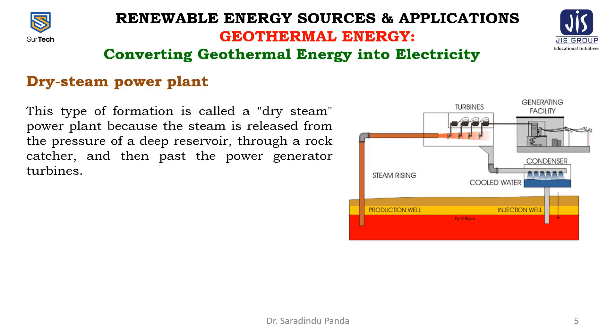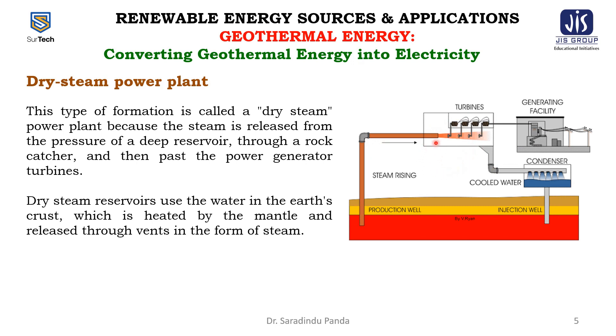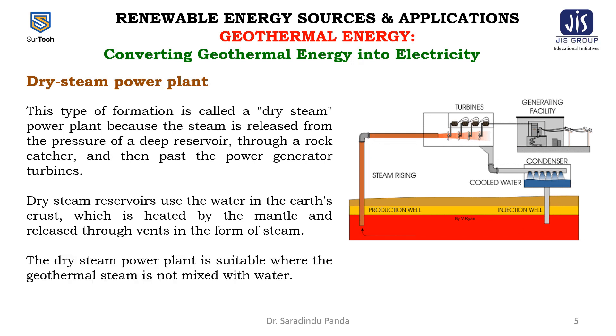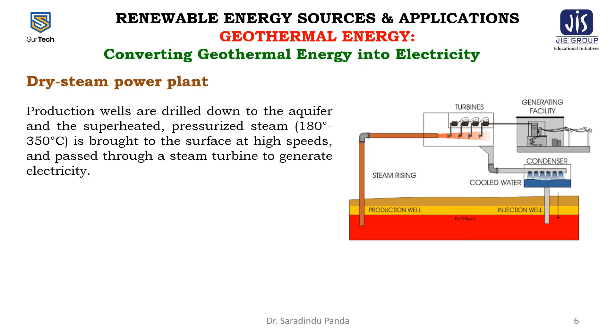This type is called a dry steam power plant because the steam is released from the pressure of a deep reservoir through a rock catcher and then past the power generator turbines. The dry steam reservoirs use water in the earth's crust which is heated by the mantle and released through vents as steam. The dry steam power plant is suitable where geothermal steam is not mixed with water. Production wells are drilled down to the aquifer, and superheated pressurized steam at 180°C to 350°C is brought to the surface at high speeds and passed through a steam turbine to generate electricity.